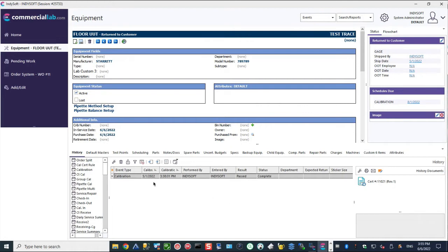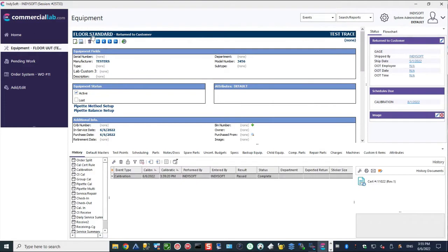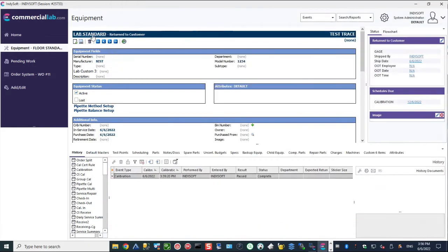Today we're going to look at building a reverse trace report. For our example data, we have a production unit that was calibrated on 5.1. This was calibrated by a floor standard, which is just a standard used on a regular basis to do the calibrations of production equipment, and it was calibrated on 6.6 using the lab standard.